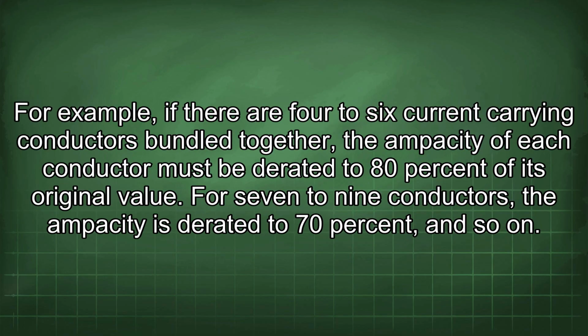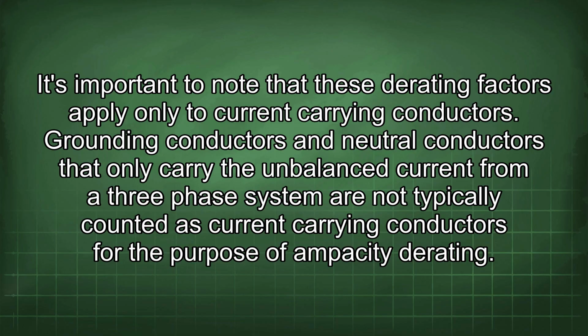310.15b3. For example, if there are 4 to 6 current-carrying conductors bundled together, the ampacity of each conductor must be derated to 80% of its original value. For 7 to 9 conductors, the ampacity is derated to 70%, and so on. It's important to note that these derating factors apply only to current-carrying conductors. Grounding conductors and neutral conductors that only carry the unbalanced current from a three-phase system are not typically counted as current-carrying conductors for the purpose of ampacity derating.